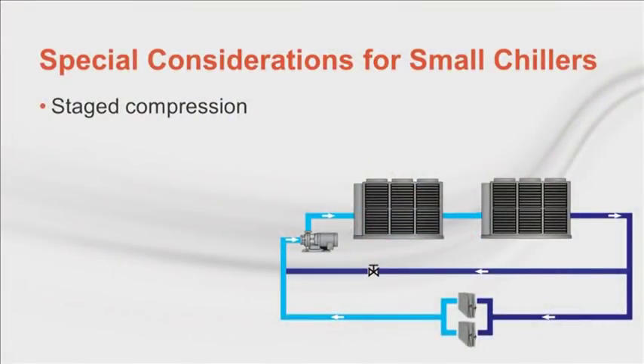When you put chillers in series that have staged compression, like with scroll compressors, the upstream and downstream circuits tend to fight each other. The upstream chiller makes set point minus a differential for long enough, turns off a compressor, and the downstream chiller sees that as a load increase and starts a compressor. Then the upstream chiller restarts a compressor and the downstream chiller shuts one off. Carefully setting up the chillers can minimize this interplay.